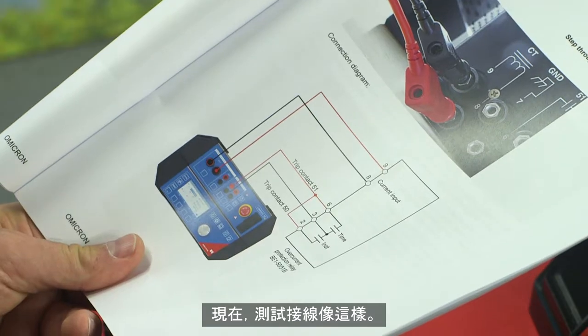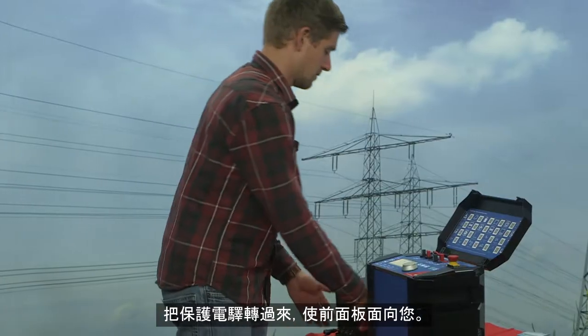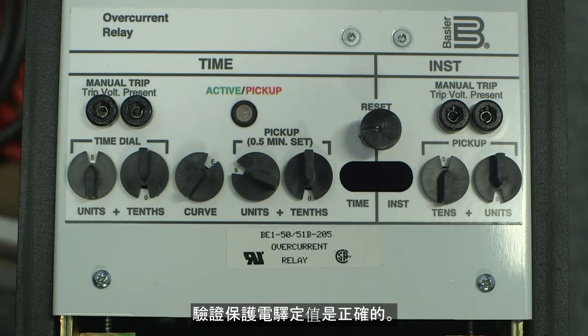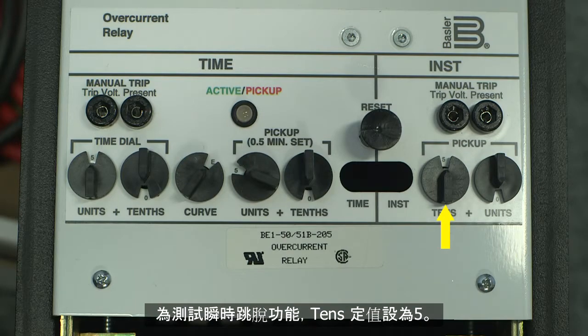Now the circuit looks like this. Turn the relay so that the front panel is facing you. Verify that the relay settings are correct. Set the time dial to 5, the curve to E, and the pickup to 5. The tens setting should also be set to 5 for the instantaneous trip.